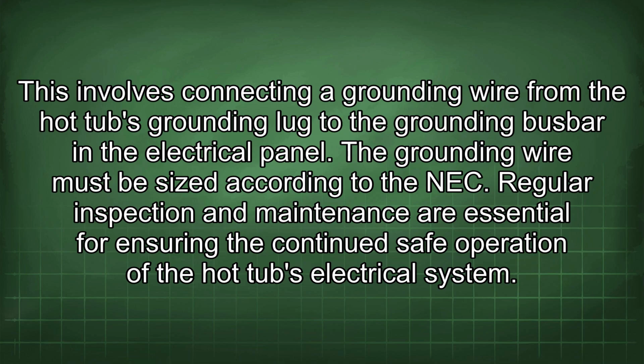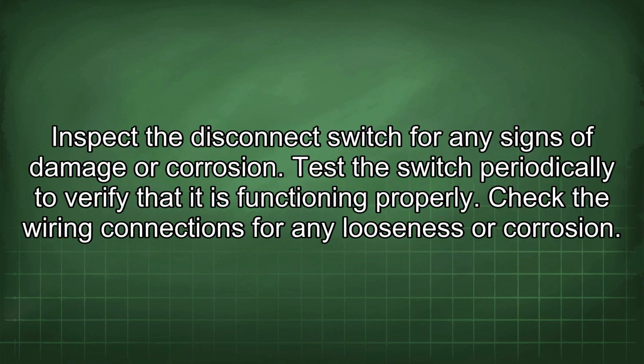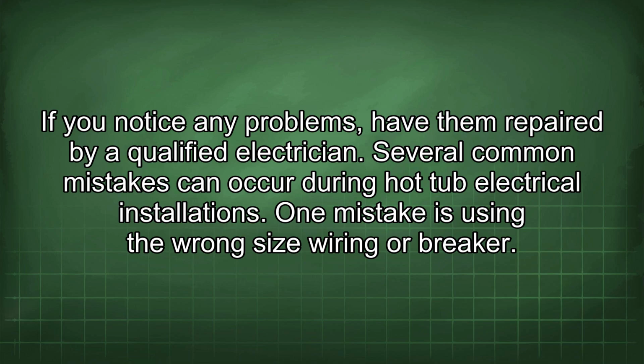Regular inspection and maintenance are essential for ensuring the continued safe operation of the hot tub's electrical system. Inspect the disconnect switch for any signs of damage or corrosion. Test the switch periodically to verify that it is functioning properly. Check the wiring connections for any looseness or corrosion. If you notice any problems, have them repaired by a qualified electrician.